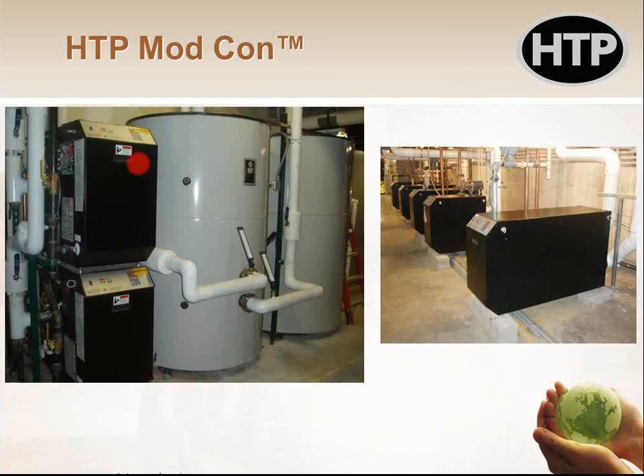Sometimes we also use them to directly feed domestic water. So instead of doing the indirect tank like I talked about before, if we do an apartment building like this one on the left over here, we might just have the boilers run domestic water right through the boiler heat exchanger and into the tank. That way we don't have the penalty loss for the double wall heat exchanger or single wall heat exchanger for that matter. But the one thing it does is reduce the warranty if you use straight city water instead of recycled boiler water. So instead of a 10-year, you get a 5-year warranty, which is still better than a typical copper boiler that you might use for domestic.